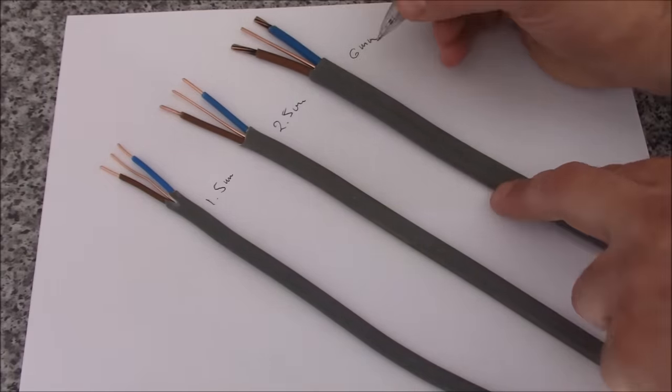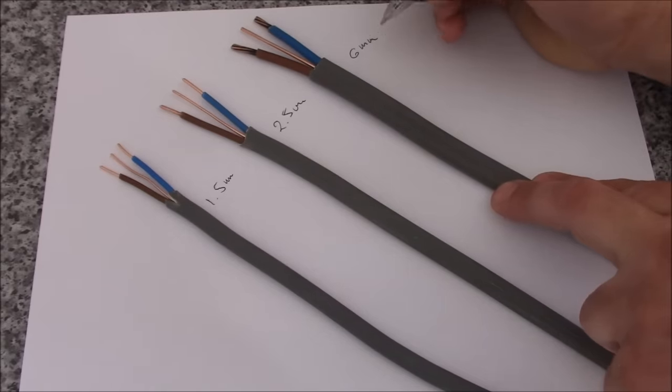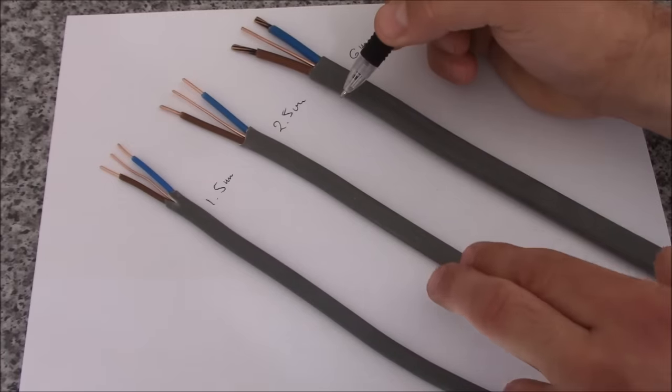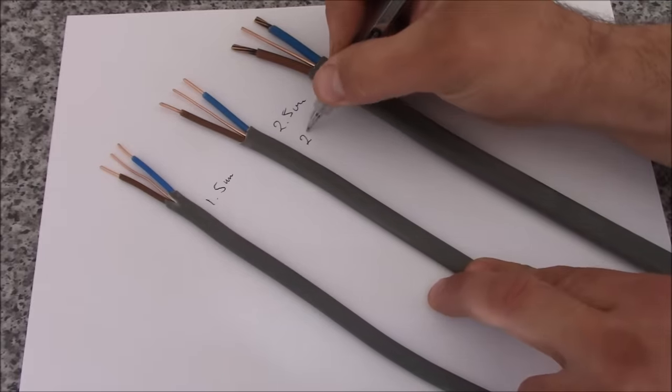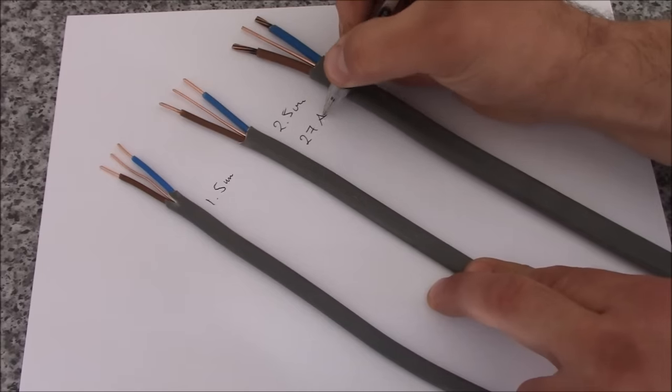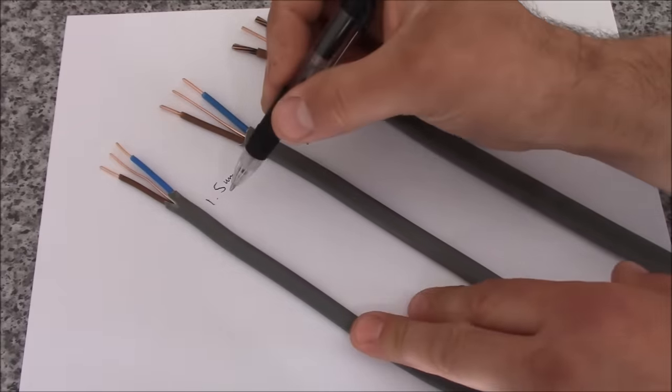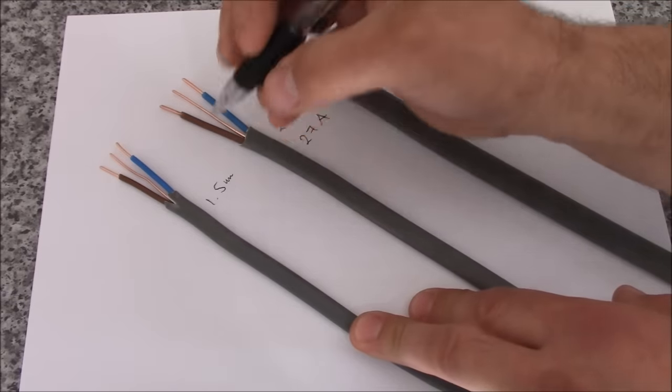And for example the thick one, the 6 mm cable, the current carrying capacity is 47 amps. We measure this in amps. The 2.5 is 27 amps. And the 1.5 is 20 amps.